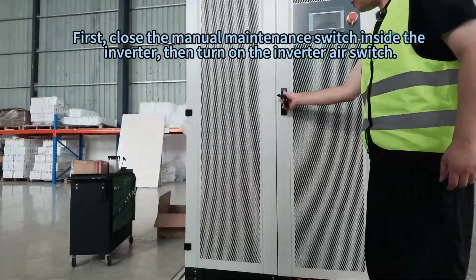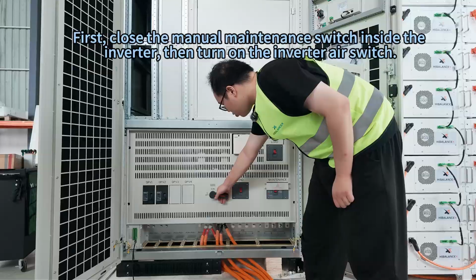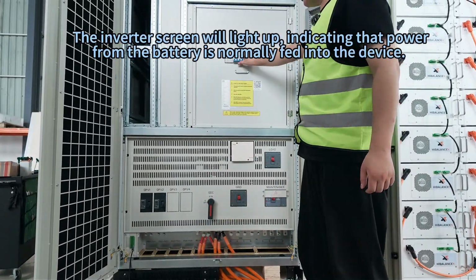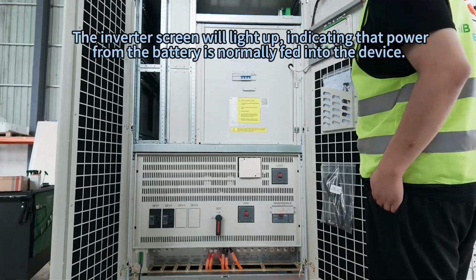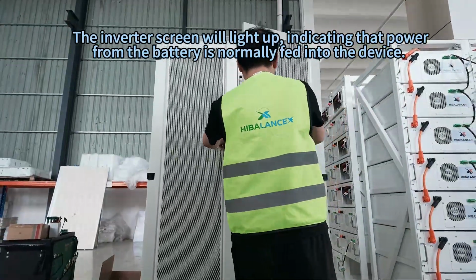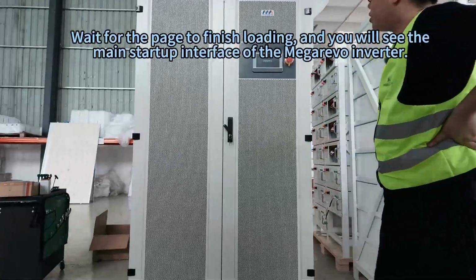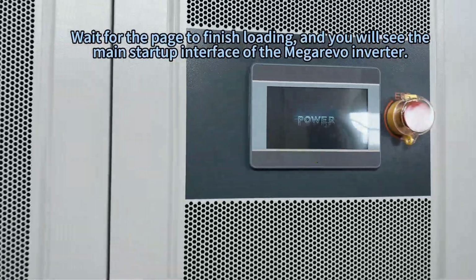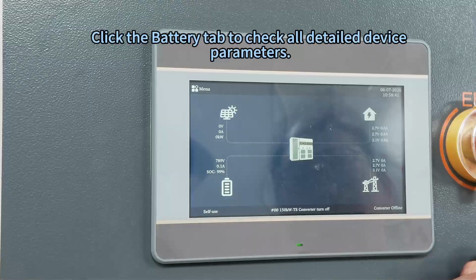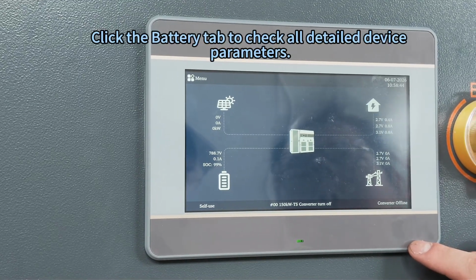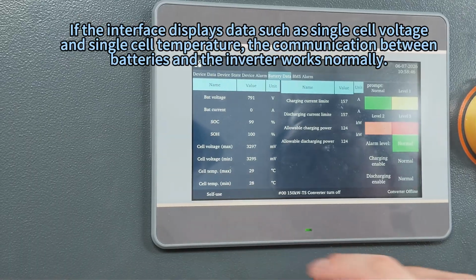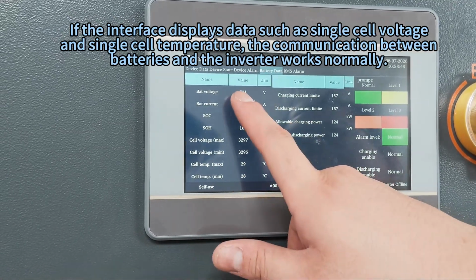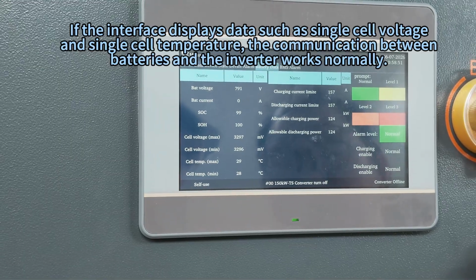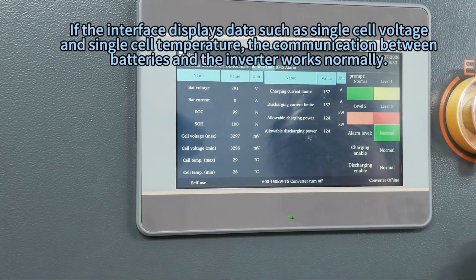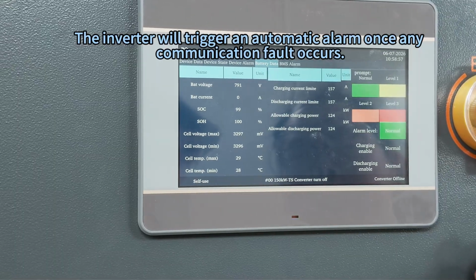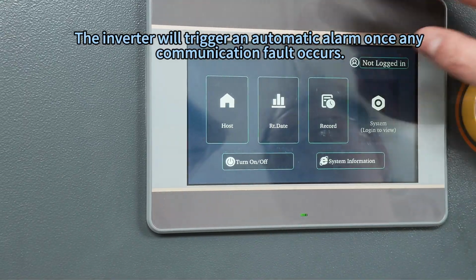First, close the manual maintenance switch inside the inverter, then turn on the inverter air switch. The inverter screen will light up, indicating that power from the battery is normally fed into the device. Wait for the page to finish loading, and you will see the main startup interface of the Megarevo inverter. Click the Battery tab to check all detailed device parameters. If the interface displays data such as single-cell voltage and single-cell temperature, the communication between batteries and the inverter works normally. The inverter will trigger an automatic alarm once any communication fault occurs.